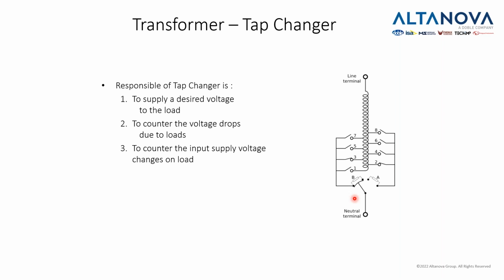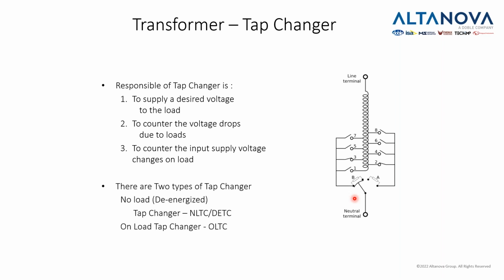Apart from windings, we also have a tap changer, which is responsible to supply a desired voltage to the load. So for example, sometimes if the load is very low, the voltage may go too high, so we would want to reduce that. So we would play with the tap, as we call it. So the tap changer is a voltage regulator. Of course, if the voltage is too low, then we can also work on that and change the position of the tap. The tap changer is important because it is the only mechanical movable part of the transformer, and it's seen quite often that it can break because it moves.